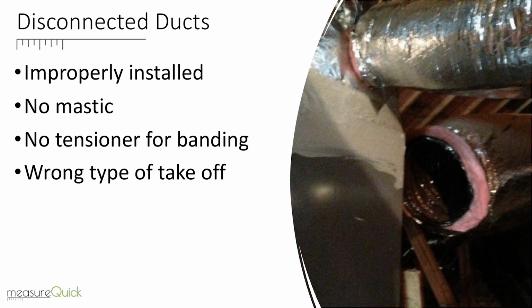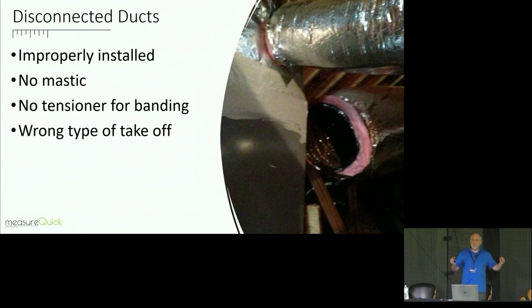Disconnected ducts, right? I don't know how many times I've seen this on systems where I've put my probes on there. Again, I see low capacity. I'm like, why am I getting this low capacity? Well, MeasureQuick will pick up duct leakage issues. So if you have a return that's disconnected, and let's just think about it, how would MeasureQuick pick up a return duct leak? What are some symptoms that we're going to see on that?